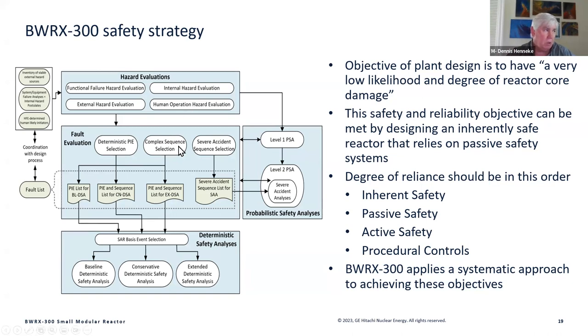They also include other events such as human-induced events, all the hazard events and combinations of hazard events, as well as complex sequences of events such as loss of offsite power followed by failure of all your diesels, station blackout, right?